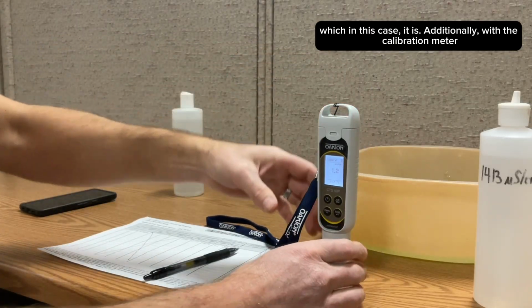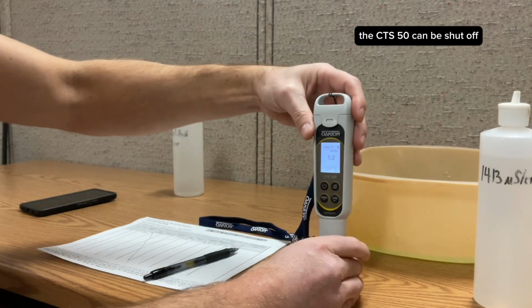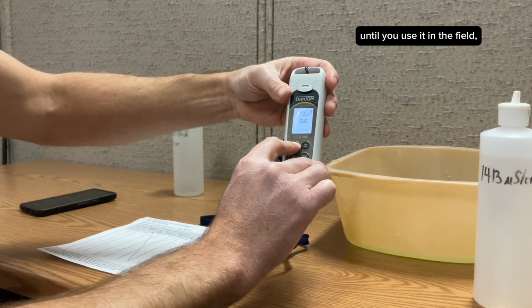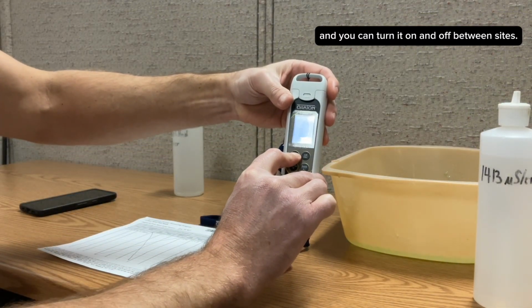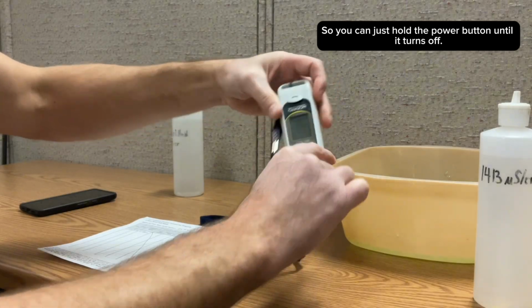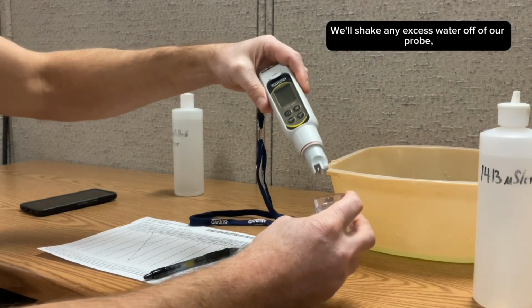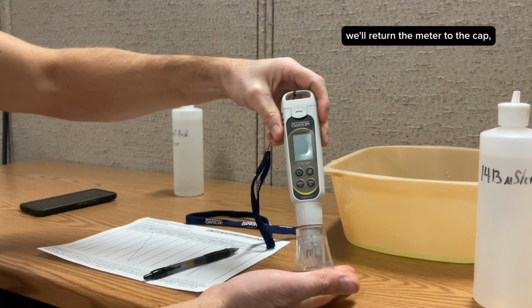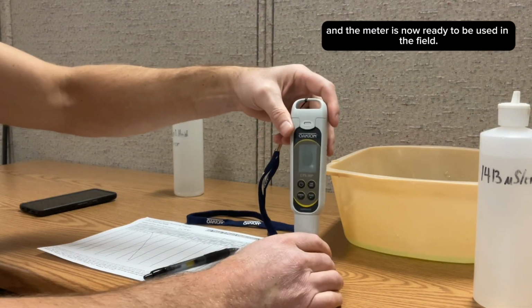Additionally, once you've completed the calibration, the CTS 50 can be shut off until you use it in the field, and you can turn it on and off between sites. So you can just hold the power button until it turns off. We'll shake any excess water off of our probe. We'll return the meter to the cap, and the meter is now ready to be used in the field.